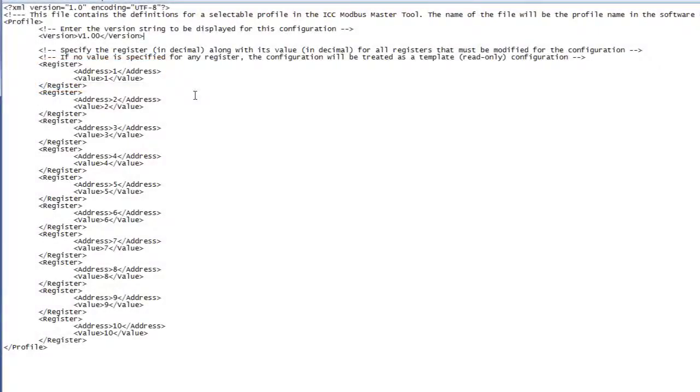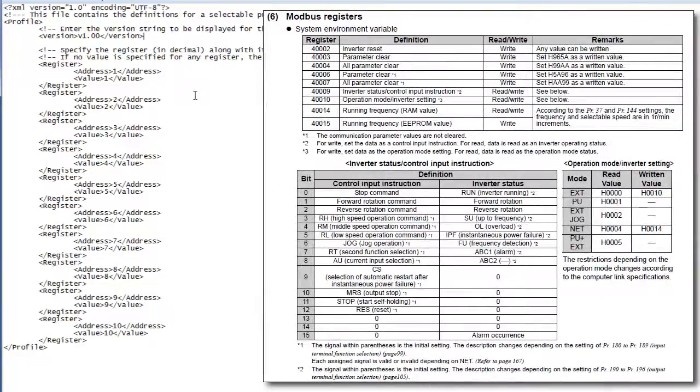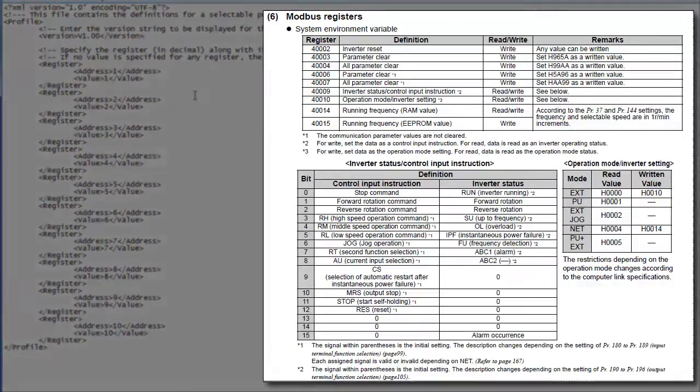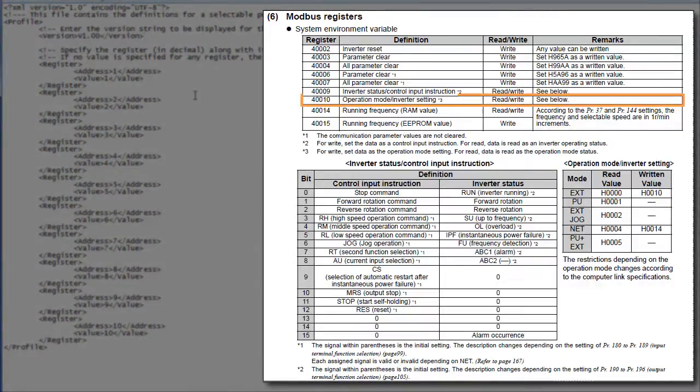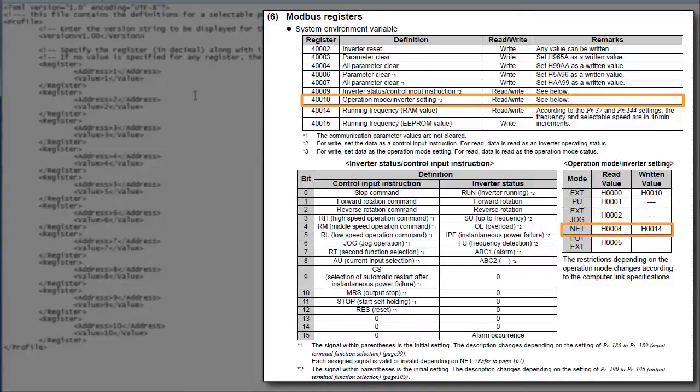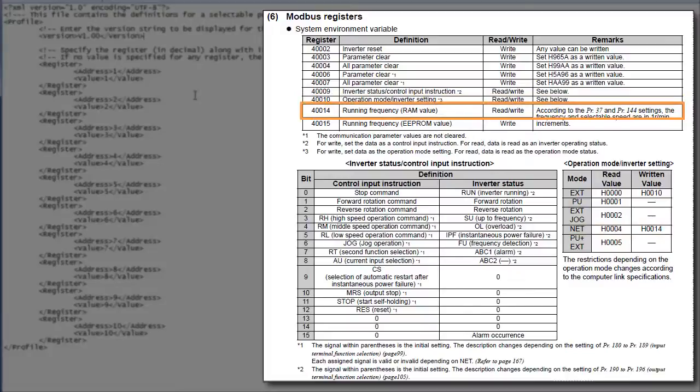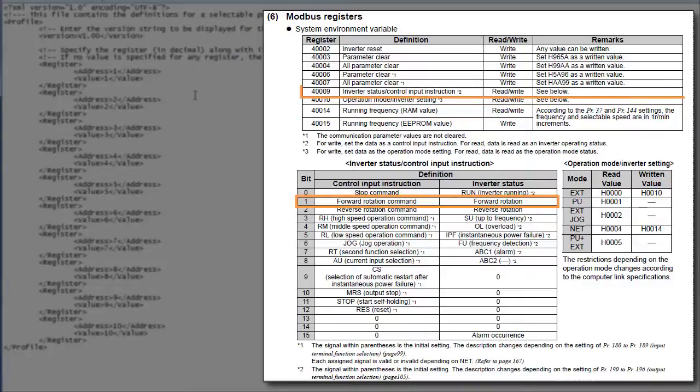For this tutorial, we're going to create a profile that will start running an inverter at 60 Hz. This is the Modbus register map for our inverter. To do this, we need to modify three parameters. The operation mode, which we'll set to network to tell the inverter to accept commands from the network. The running frequency, which we'll set to 60 Hz. And we'll need to set the run bit in the control input instruction.